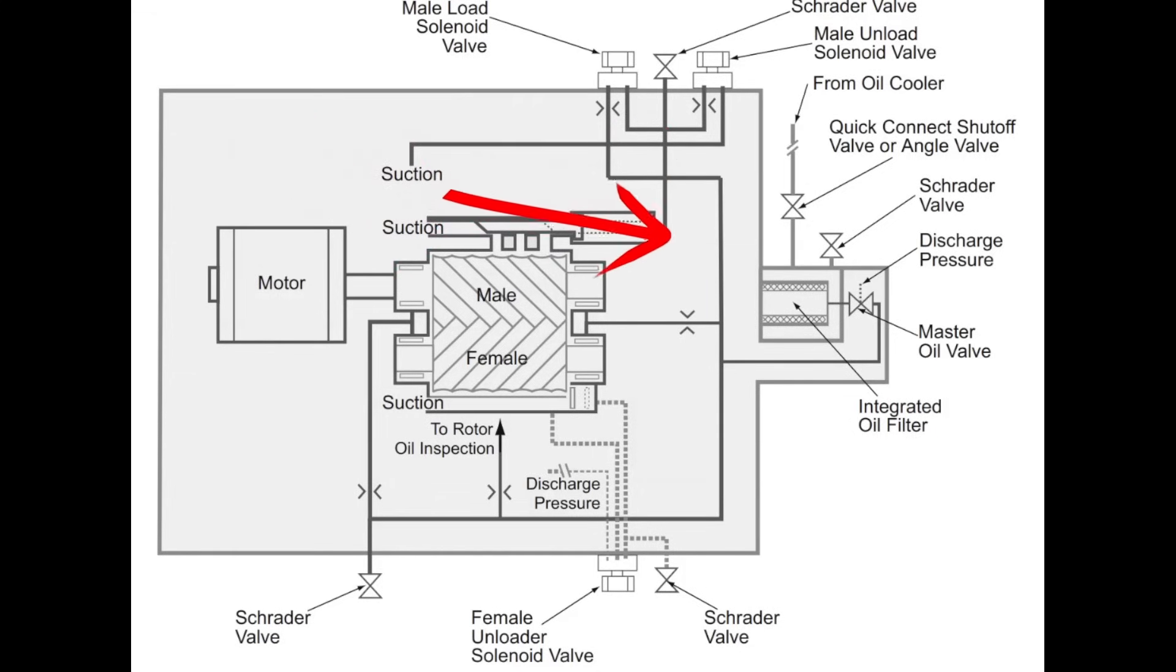And the process of that oil getting drawn back off into suction pulls that slide back to get it back into an unloaded state. So that is your male load and unload solenoids and how they differ from your female unloader solenoid and what their primary functions are in the circuit.